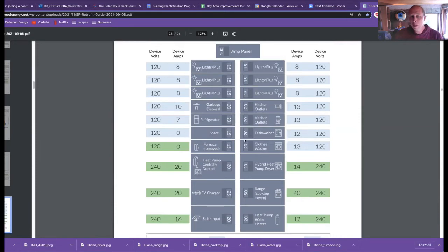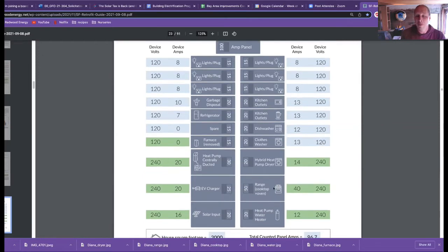So in blue are all the things you just normally have as wires. But we were trying to keep this on 100 amps, so this is one way of doing that, just one of the many, where he has a hybrid heat pump dryer, so that is electric resistance. The one I was like, don't do it. He does have, in here, a combined range. Diana, because you have ovens on the wall and a range, you're going to have to have special circuits for each. It takes up more power.